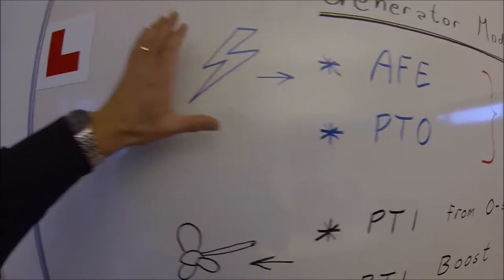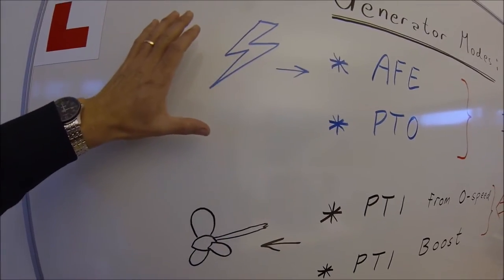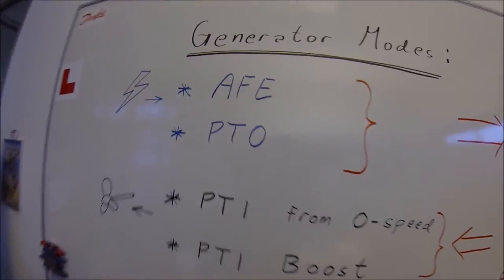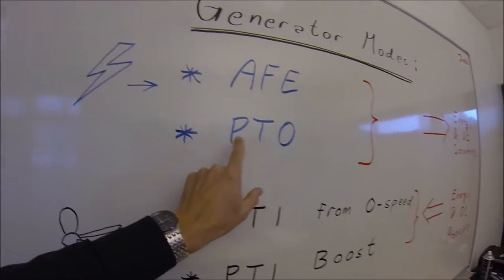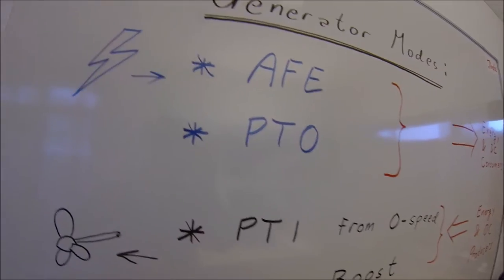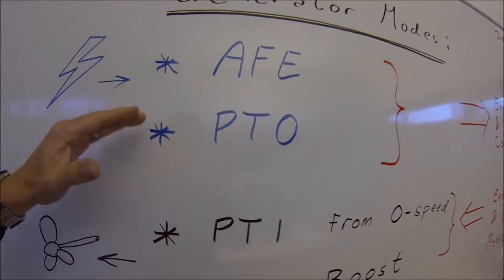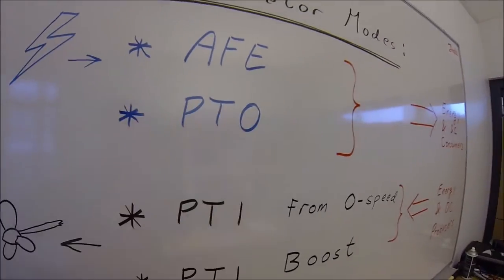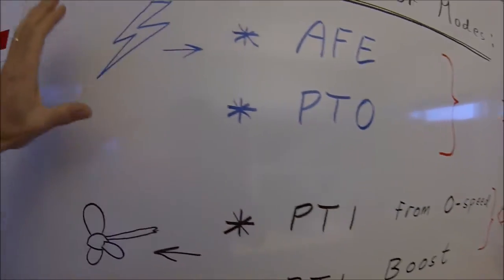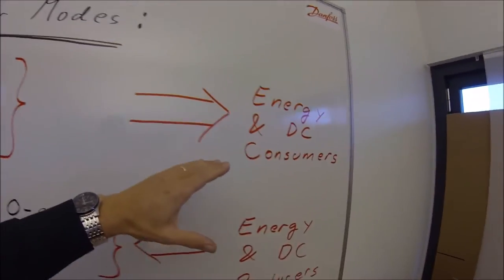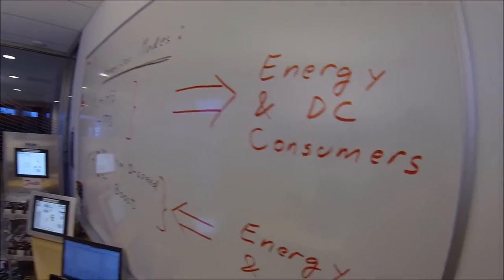To take power out of the generator and put it to its consumers, the most common way to do that is in the power take out mode. You can also utilize the active front end mode, but the power take out mode — where the drive produces a set DC voltage for its DC bus — is the most common way to do it.